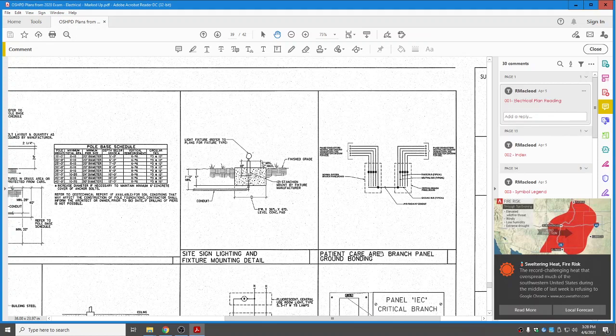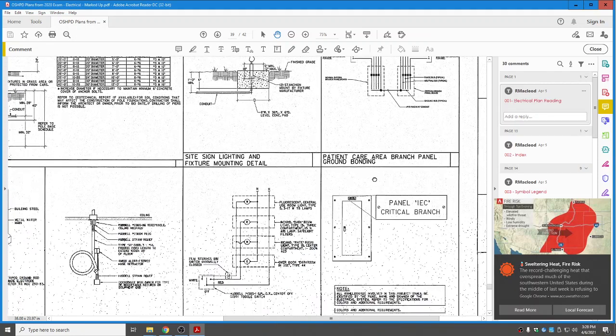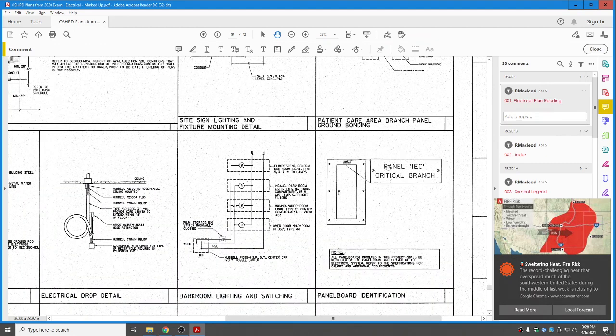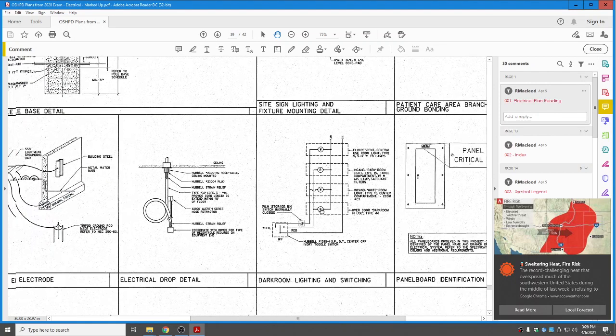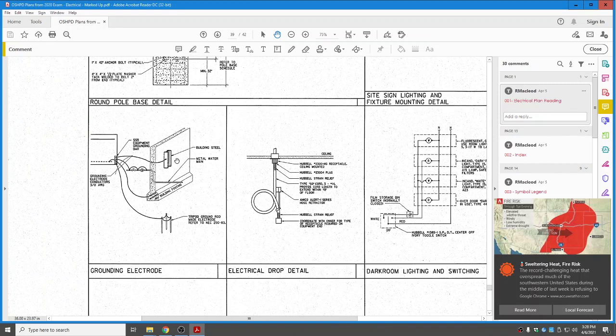patient care area branch panel ground bonding, typical, what's your typical electrical panel, how it should be labeled. This is a very old label. Today's labels probably have about 9 different things that need to be mentioned on an electrical panel per code. We have a ground electrode system showing how to connect a switchboard to an Ufer ground, to the water piping, or to the building steel, and what size grounding electrodes you need to use.